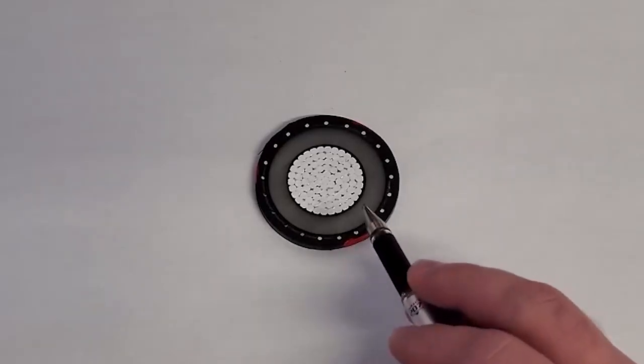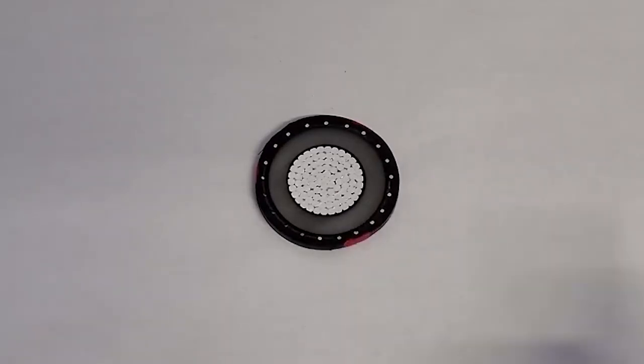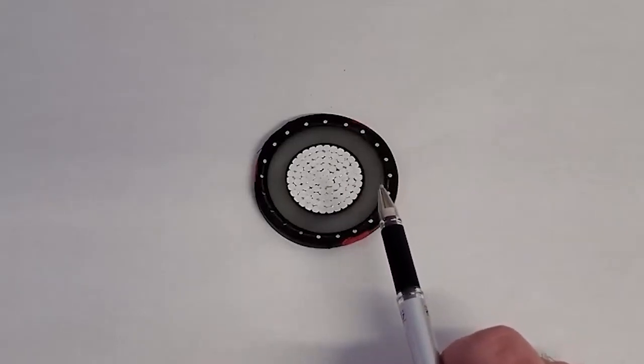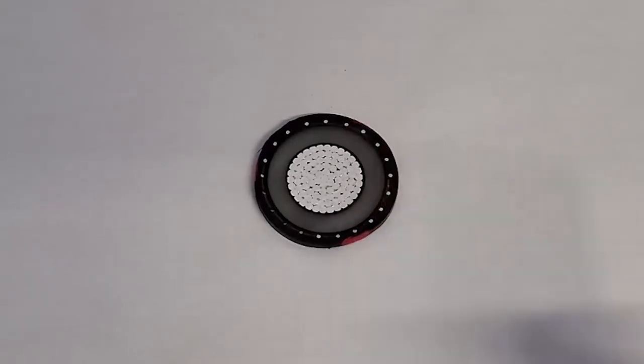So we'll talk about the conductor first. So this is an aluminum conductor. Obviously there's copper. It's mainly copper and aluminum. That's your two different types of wire for this industry. Silver is actually the most conductive metal, but of course, silver cable would be ridiculously expensive and would never offset the losses. Then next you have copper, then gold, and aluminum.